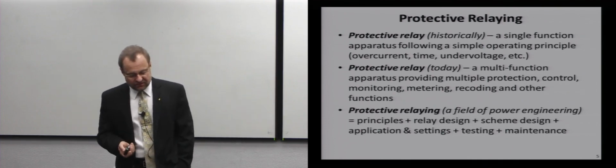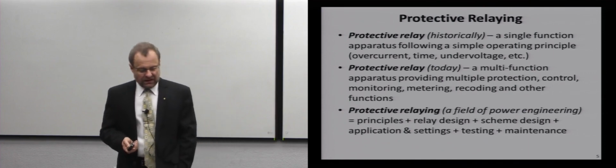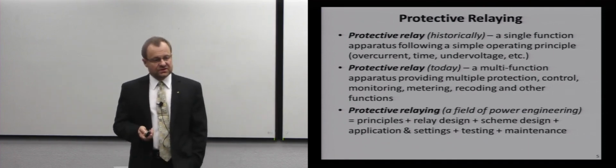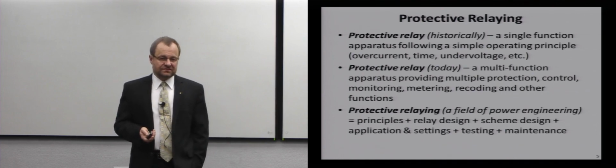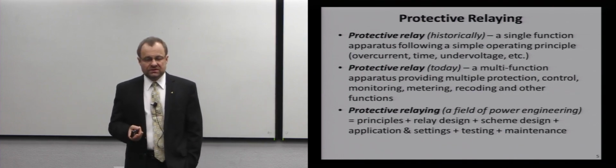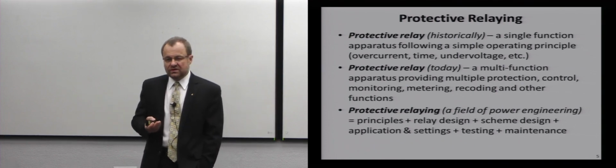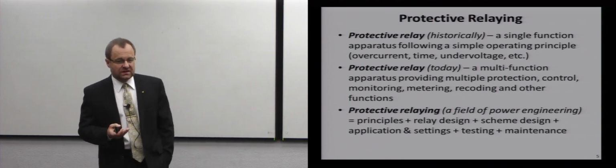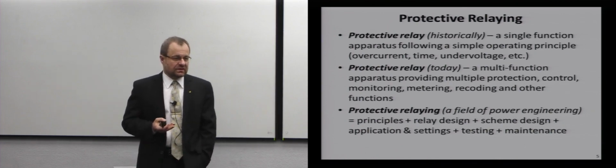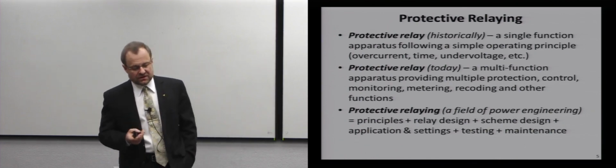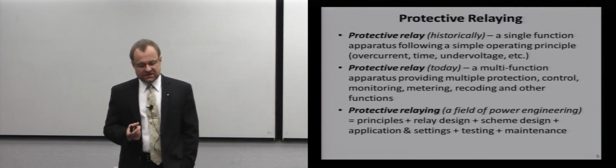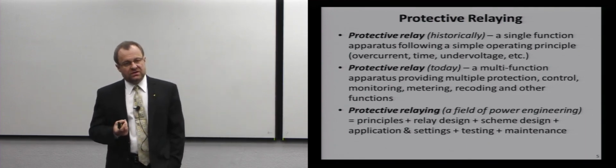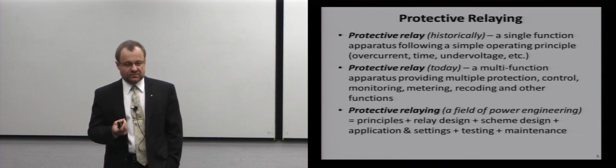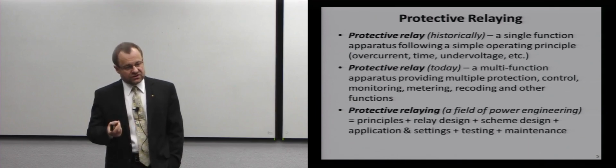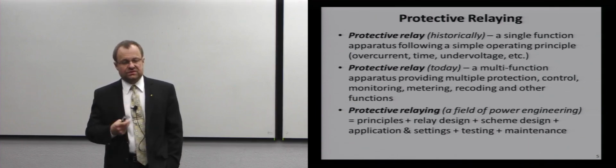Protective relaying is a field of power engineering, I would argue, and it consists of a couple of things. It consists of principles. To call yourself a protection engineer, you have to know what the differential function is. You have to know the principles of distance protection, right? This is, in a way, applied mathematics, or basics of electrical engineering. Then another aspect of protective relaying is relay design, meaning you have people who are able to design those devices to actually follow principles, to be an actual differential relay or an actual distance relay, right?